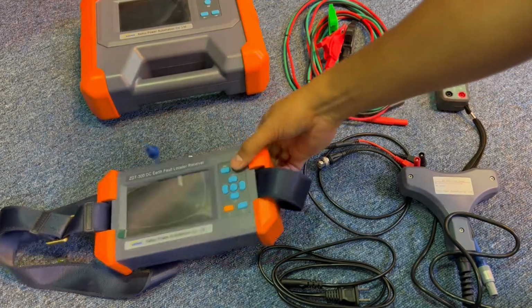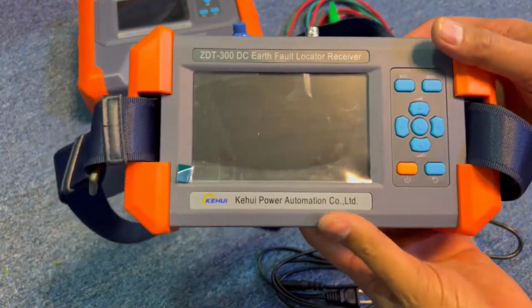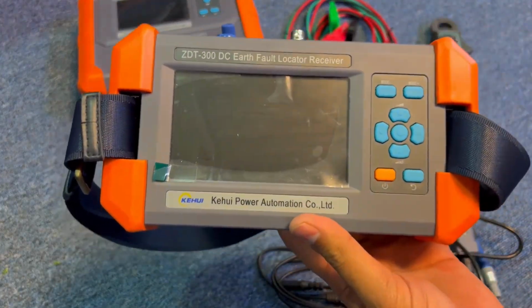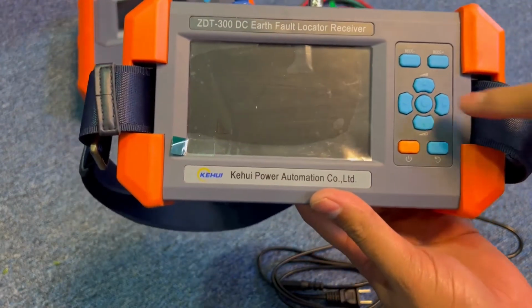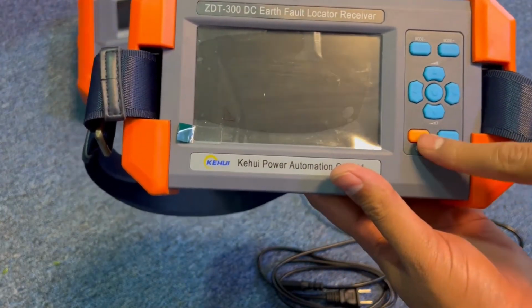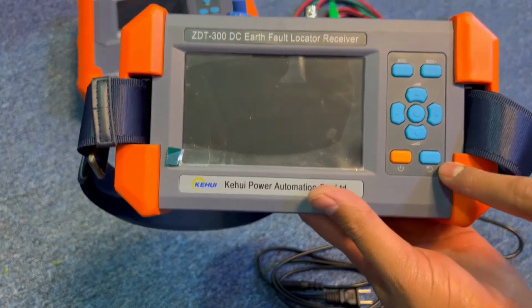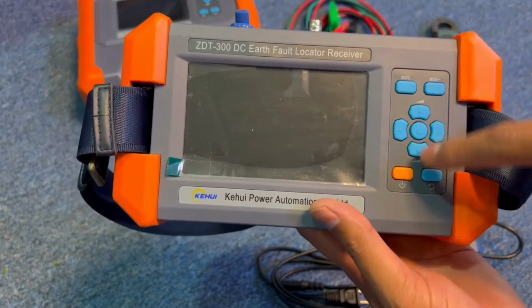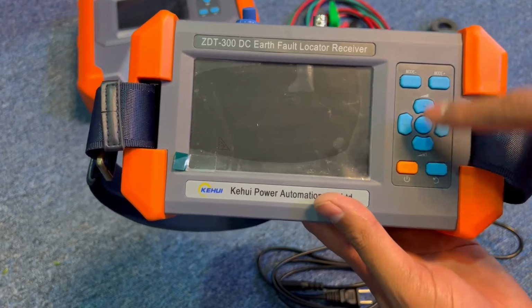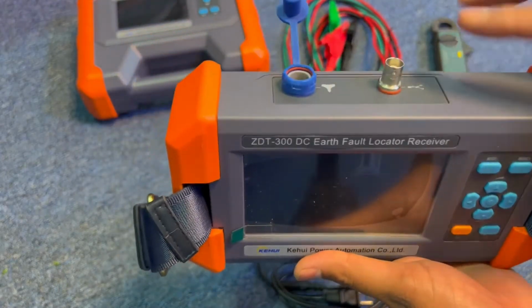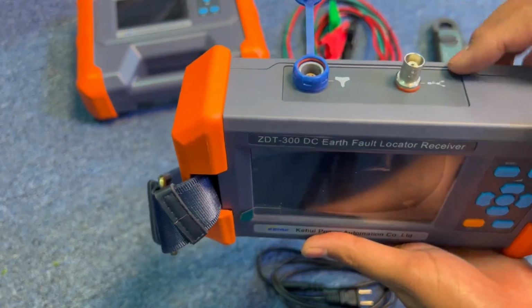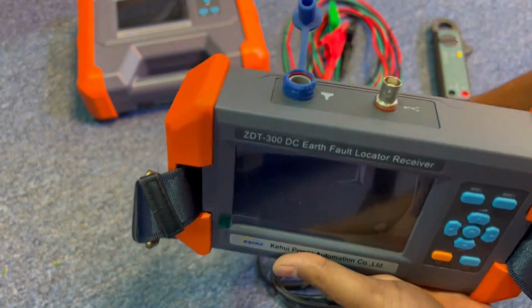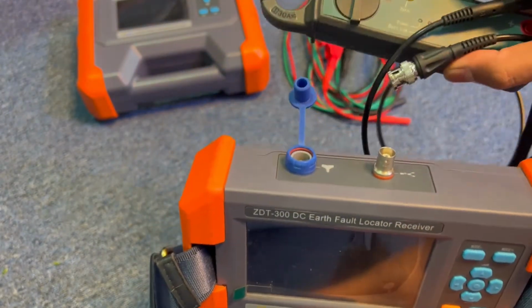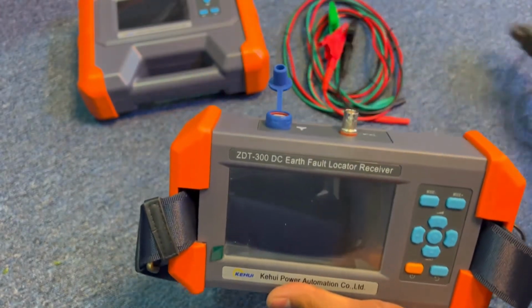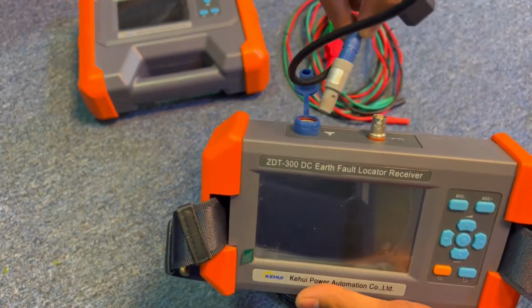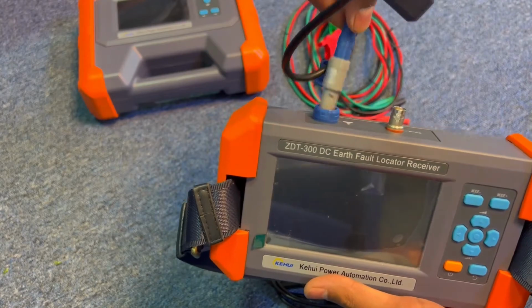And then if you go to the receiver unit, you can change to a different waveform and see what's happening in the system. This is the power on button, and this is a refresh button. You can increase and decrease the gain through this button. This receiver unit has two channels. One is a standard channel which can be used with a standard clamp, and then you have another channel you can use with a bigger clamp.